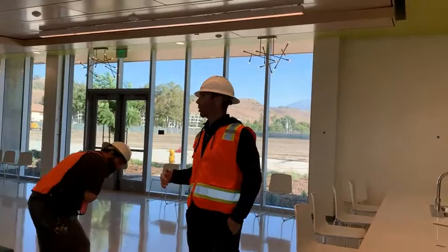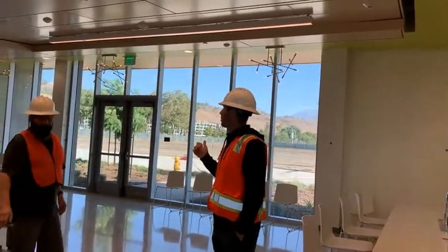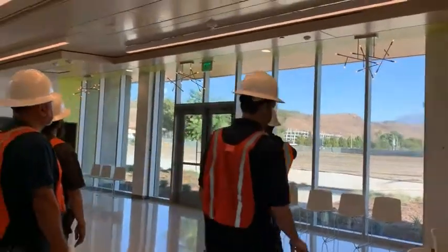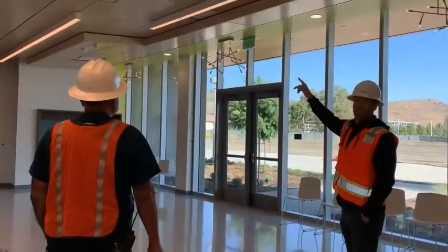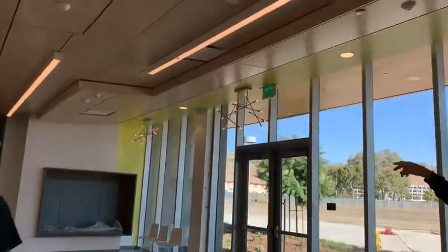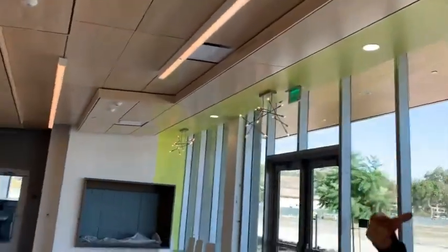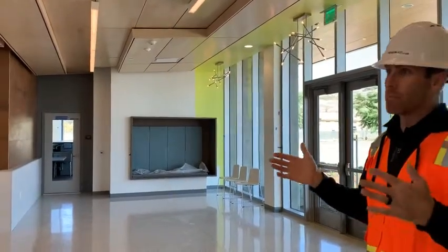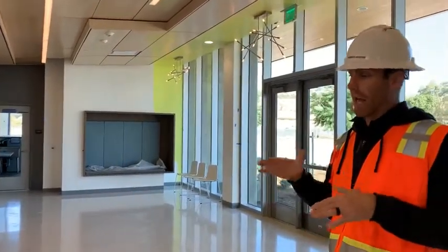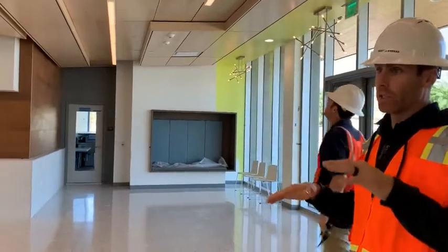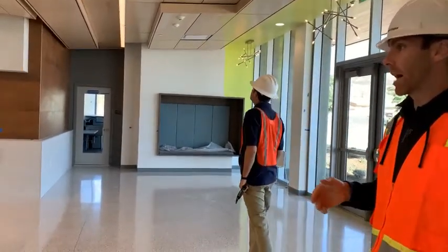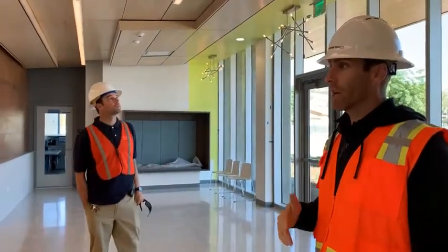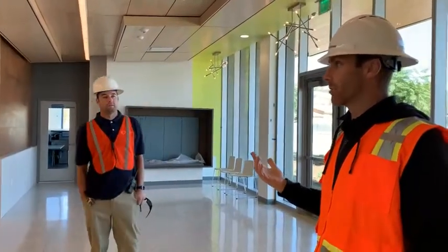Okay. What you are going to see in areas like this, though, is the daylight harvesting. As you can see, all this is kind of dim right here. What happens with daylight harvesting is it's supposed to be realistically a mixture. It's getting light coming in, and what they're doing is lowering the artificial light because there's more natural light coming in. So we're not looking to turn off the lights. The lights aren't going to turn off. They're just going to dim as the sun comes up through the day.